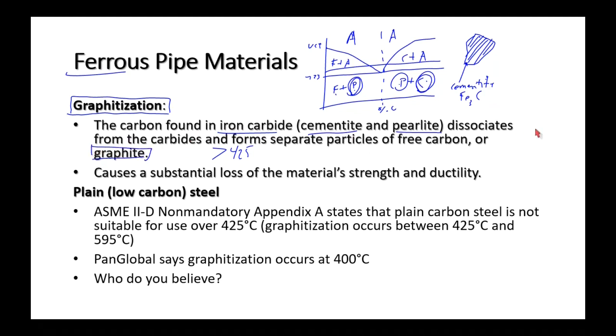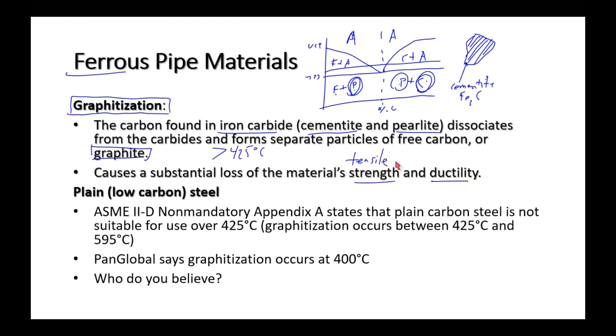We saw graphite before in gray cast iron, where graphite along grain boundaries makes it prone to fracture under tension — graphite is weak under tension. Above 425°C, graphitization is the process whereby iron carbide reverts to graphite, causing a loss in tensile strength and ductility. Graphitization is how plain carbon steel becomes weak at high temperature over a prolonged period.